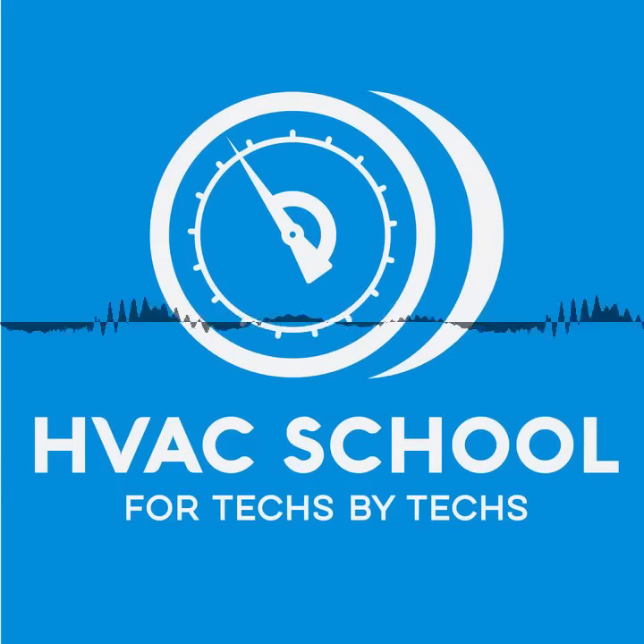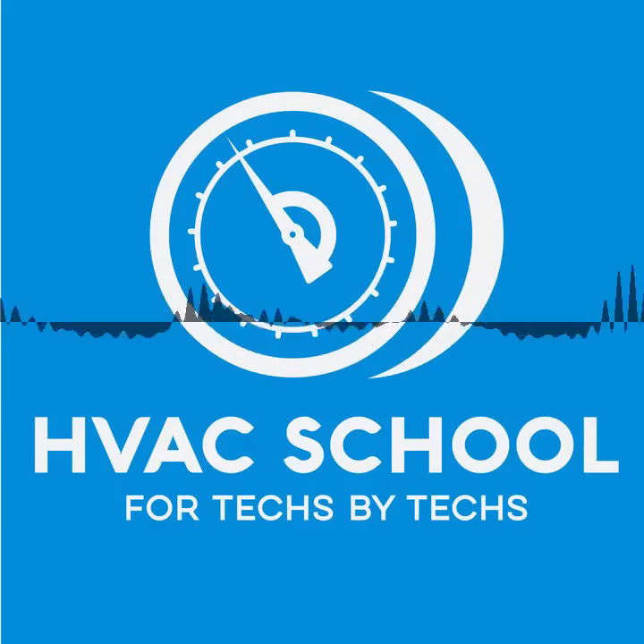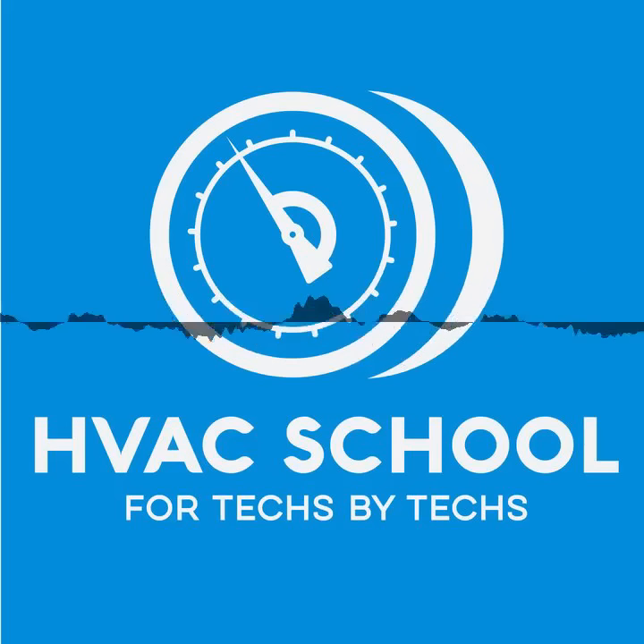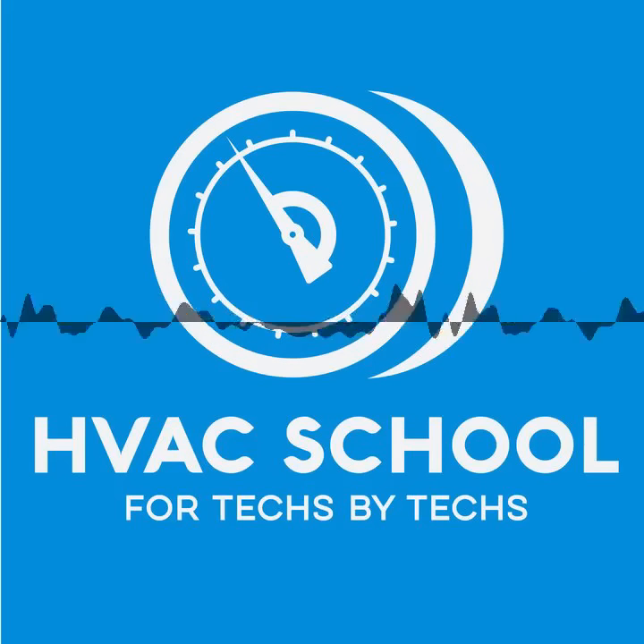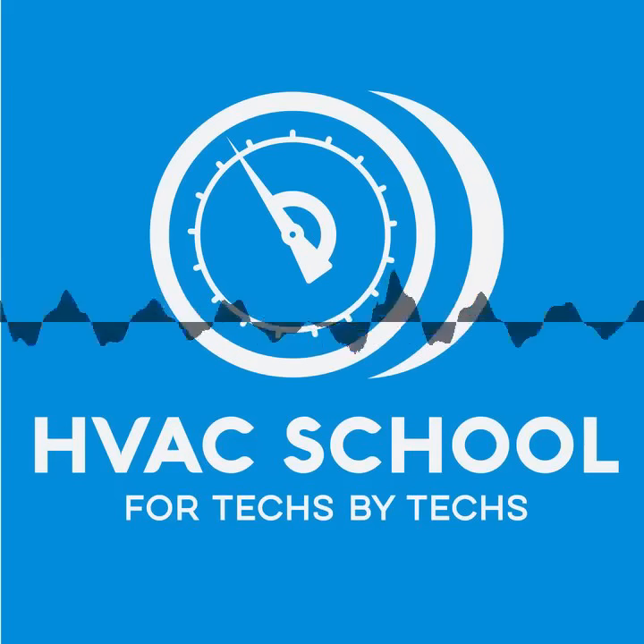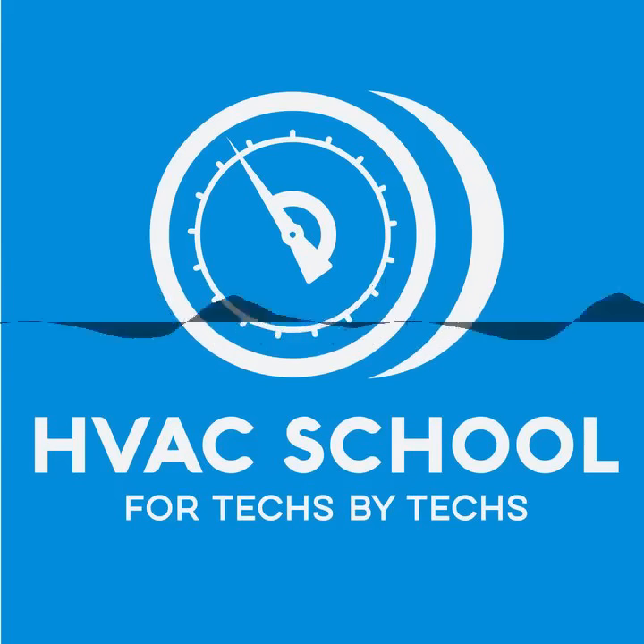But then at the VAV box itself, at the box side, this is sort of a side note here, but you can have VAV systems in which the boxes, what am I talking about? Exactly what we're talking about. You're going to have VAV boxes downstream, and they're going to be either opening and closing or modulating depending on what type you have. And they want a constant supply of 55-degree air, let's say at 1.5 static, so they know how much air is going through so they can work properly. I just got my brain twisted there, but yes. So you could have a water coil, a chilled water coil VAV system then is what we're saying. Yeah, it's really good for that.